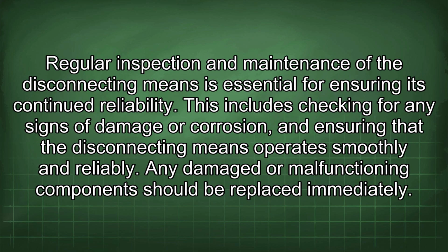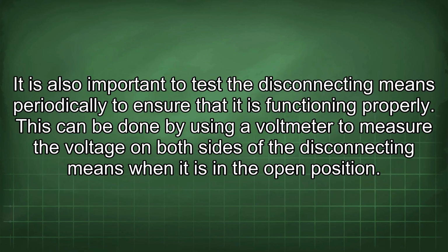Regular inspection and maintenance of the disconnecting means is essential for ensuring its continued reliability. This includes checking for any signs of damage or corrosion and ensuring that the disconnecting means operates smoothly and reliably. Any damaged or malfunctioning component should be replaced immediately. It is also important to test the disconnecting means periodically to ensure that it is functioning properly.